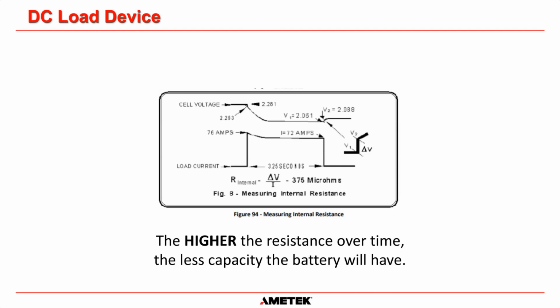So at this point here, that is when the test starts, okay? And it applies the current to start off with. And what they're looking for is where this line here starts to go flat. So when they see that this line here is going flat, that means the battery is at a steady state, okay? And then at this point here, the load is removed from the cell corder. But the interesting thing that the cell corder does is it's only looking at this very small area here, and that is an expanded view of that area.